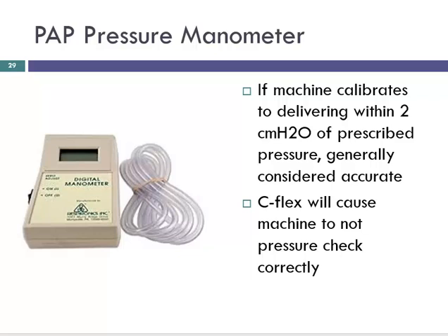When you're pressure checking a machine, if that comfort feature is on, the machine's not going to pressure check. So it's something to always keep in mind, because one of the things I do in prisons is check the integrity of their machines periodically, and you have to make sure you go in and turn the C-Flex off. I almost decommissioned a patient's machine, thinking okay, it's time to get a new one, causing the insurance company to pay, and the patient to pay all this money to get a new machine, when their machine was still working fine. I forgot to turn off the C-Flex.